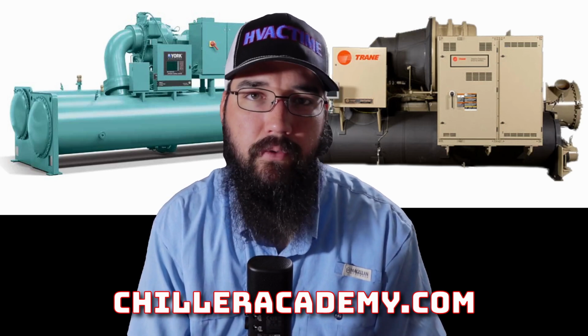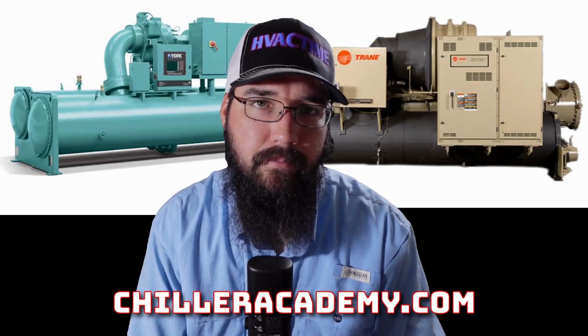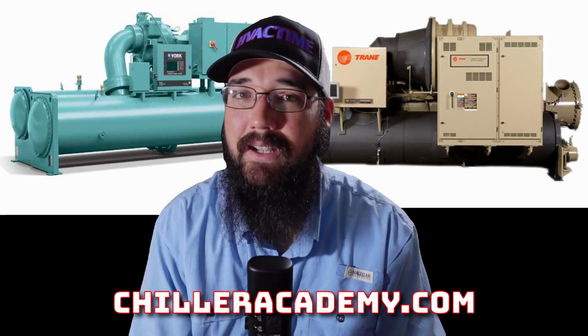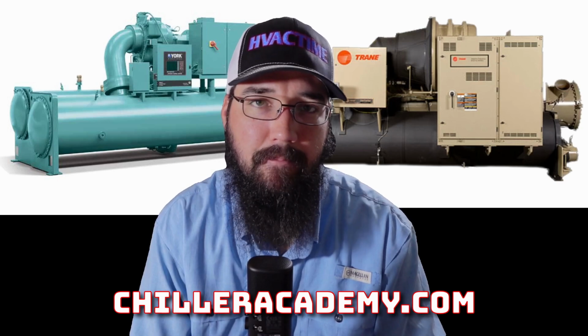So when you get into a conversation with a seasoned chiller technician, don't start talking pressures. Okay. Unless you're talking about oil differential or something like that, or differential across the compressor, or your lift, things along those lines. If you're talking about refrigerant and you're trying to just have a discussion around what is happening on the refrigerant side, it is irrelevant what type of refrigerant you have. What temperature do you have, what are your saturations, and then tell me what are your water temps. And that's going to give me a lot to work with versus you trying to communicate some kind of pressure. I don't care about pressure. All right. I care about what are your temperatures, and then we'll go off of there.